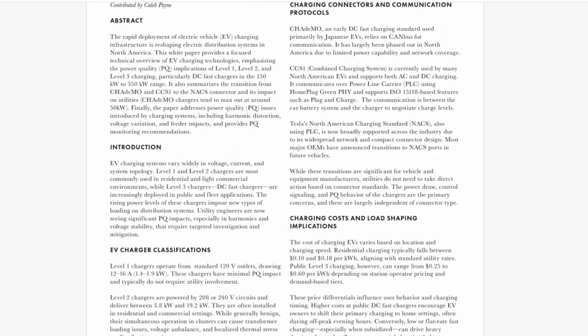There are 3 basic levels of charging. There's level 1, level 2, and level 3. Level 1 and level 2 are what you're going to find in commercial residential installations. They're either 120 or 240 volts. Level 1, for instance, is 12 to 16 amps, 120 volts. And then level 2, the 208 to 240 volt circuits can go up to, I believe, 80 amps. Those really are not big power quality headlines. The DC fast chargers are what's really changing. And so I wanted to go over the fact that CHAdeMO is being phased out in favor of these new systems because CHAdeMO was limited to 50 kilowatts, whereas the new CCS and NACS charging systems peak out at about 350 kilowatts, so about a third of a megawatt, which obviously is a drastic difference.